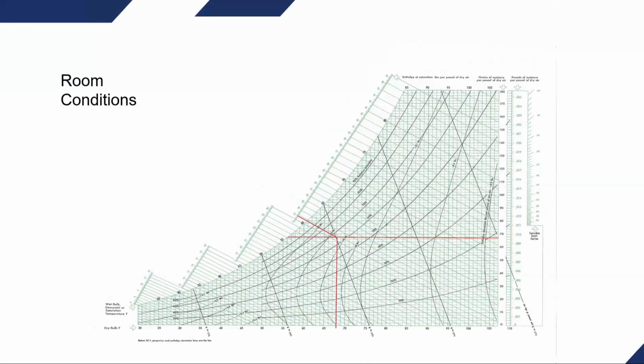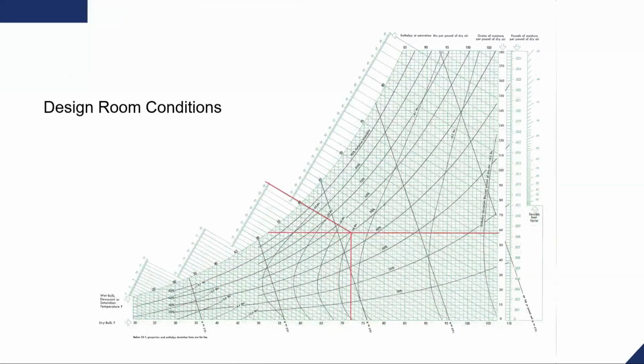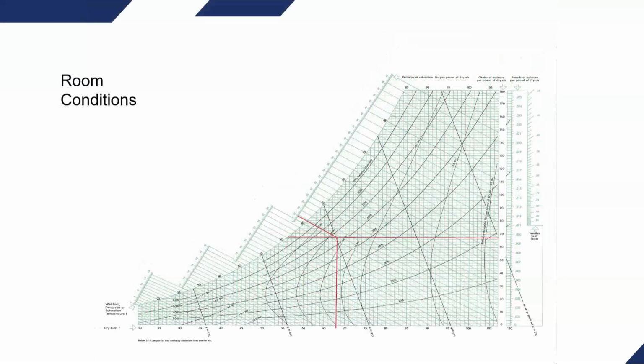Whenever we're looking at a humidity issue in a school, what we're looking at is the grains of moisture in the project. So if we go back to the design conditions, typical good room conditions, we're running about 58 grains of moisture. That's where we'd like to be. In this particular case, we are running more like 68 grains of moisture. So the key is to determine what needs to be done to get that moisture out.